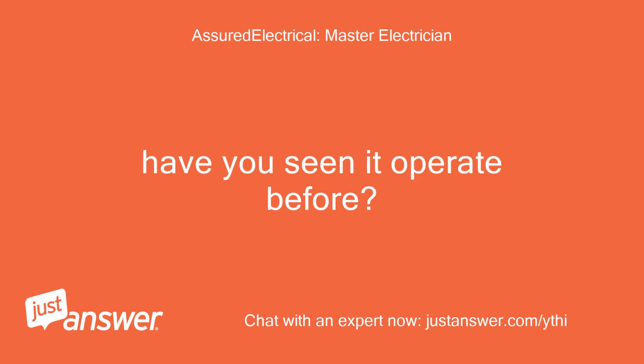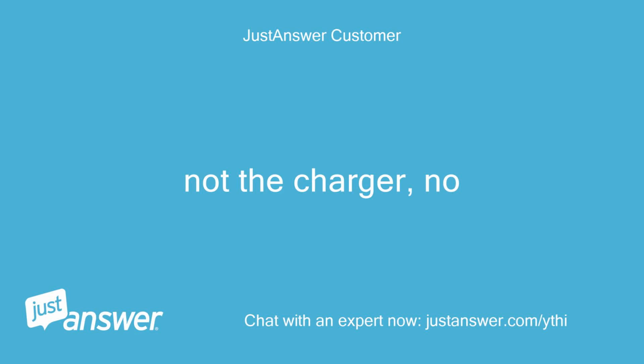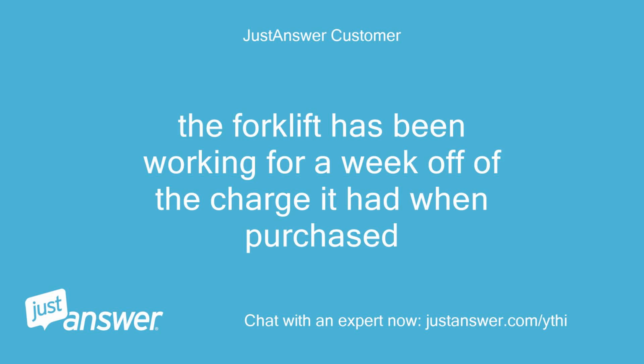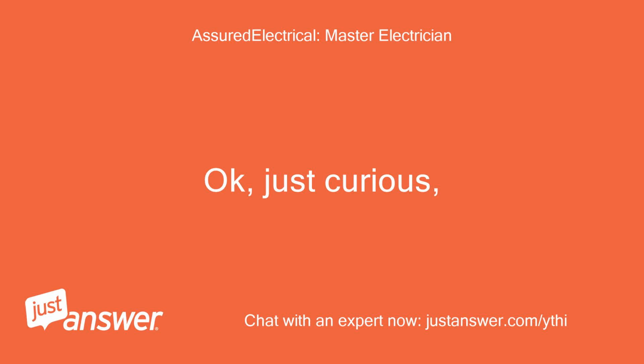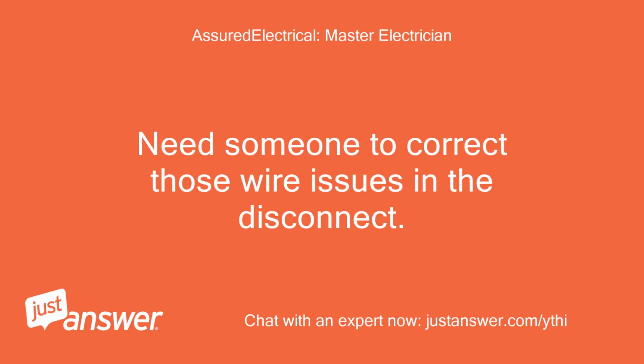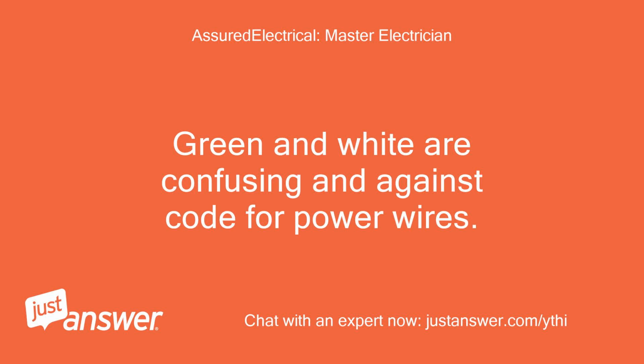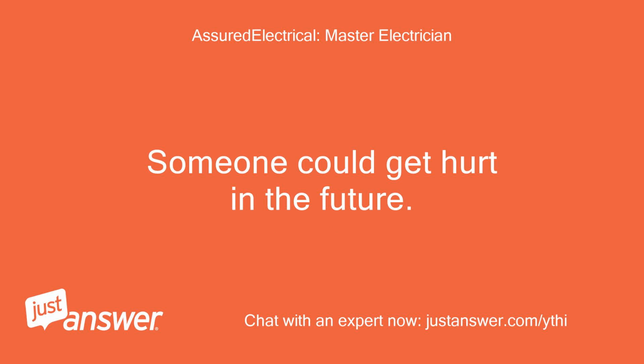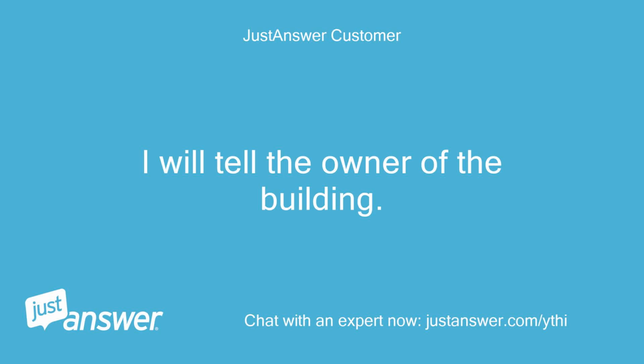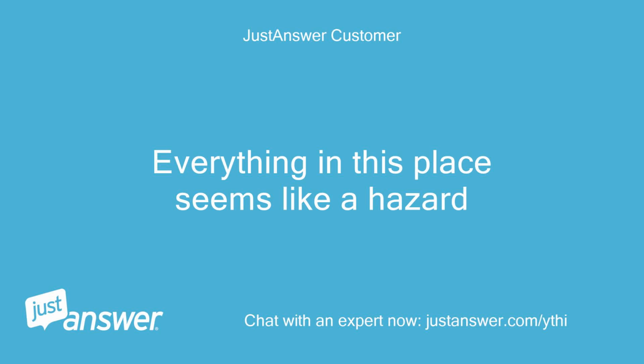Have you seen it operate before? Not the charger, no. The forklift has been working for a week off of the charge it had when purchased. Okay, just curious. Need someone to correct those wire issues in the disconnect. Green and white are confusing and against code for power wires. Someone could get hurt in the future. I will tell the owner of the building. Everything in this place seems like a hazard.